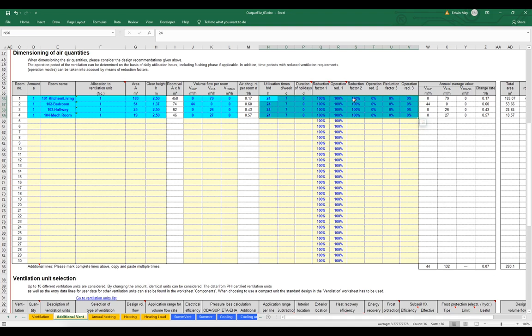We get a ternary scheduler where we have three different reduction factors and three different operation times we can input. For residential projects, it's typically sufficient to use this simplified scheduler. The calculator wants to know basically how fast, as a percentage of its maximum speed, the ERV is going to be operating, and for how long — three different speeds and three different time periods.